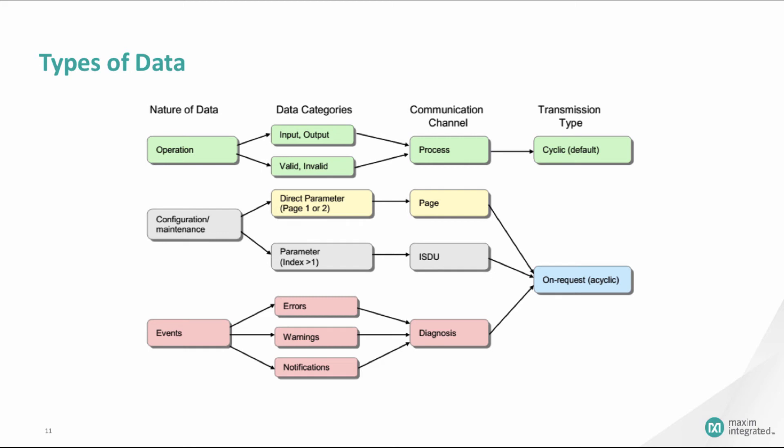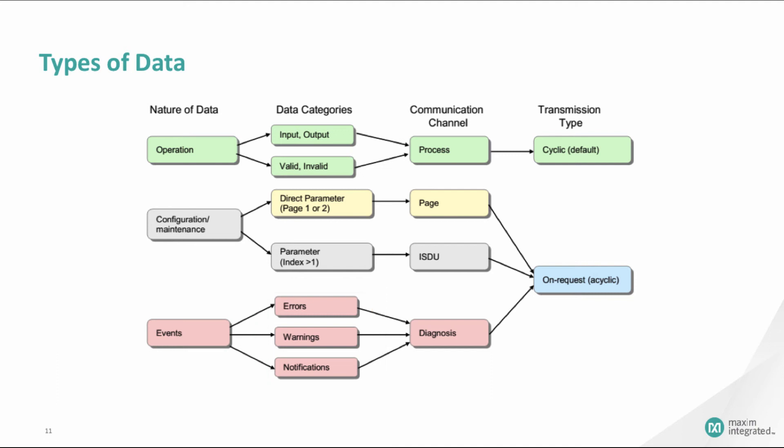IO-Link communication is either cyclic or acyclic. Cyclic data typically involves normal operation — for example, the sensor sending data to the master. Acyclic data can take one of two forms: the first is configuration or maintenance information, such as the master configuring the device after power-up or requesting device configuration before it powers down. The second is event-triggered. Events are reported with three levels of severity: notifications, warnings, and errors — for example, when a fault or error is triggered.